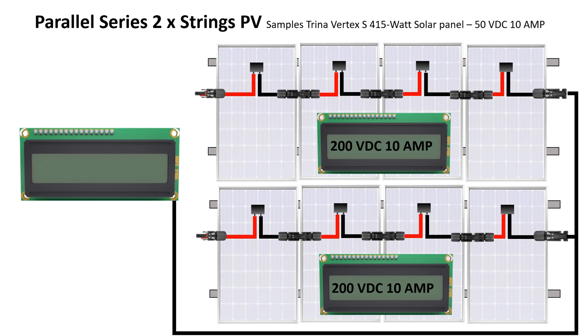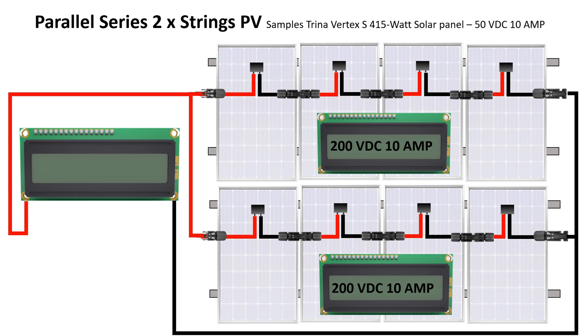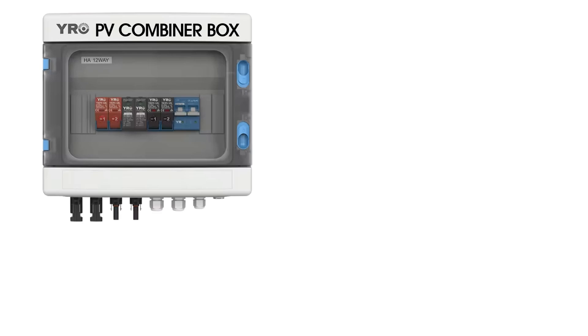To parallel the strings, you connect positive to positive and negative to negative. When you measure them in parallel, the volts stay the same at 200 volts but the amps add up, giving you 200 volts at 20 amps. That increases your power: 200 volts times 20 amps gives you an output of 4 kilowatts. The principle stays the same regardless of inverter size.